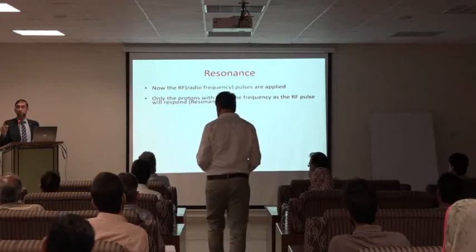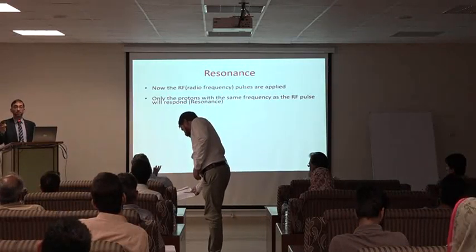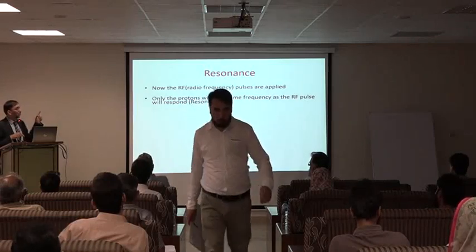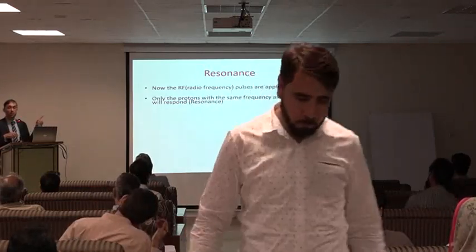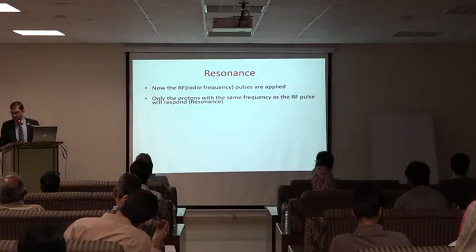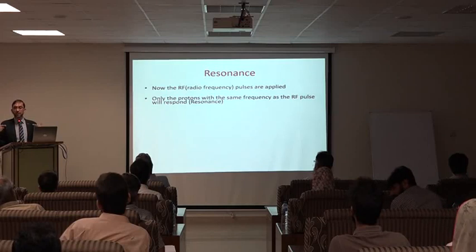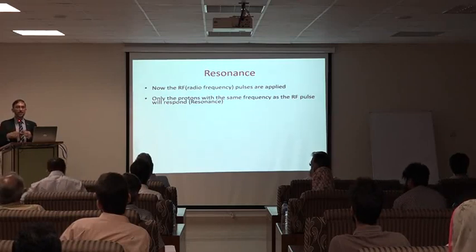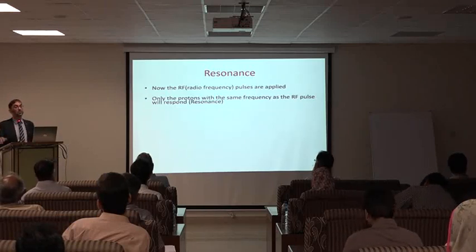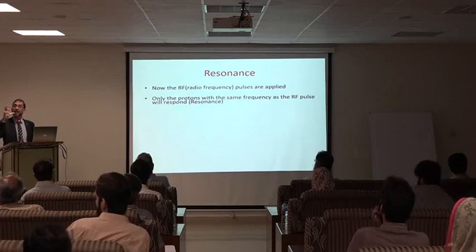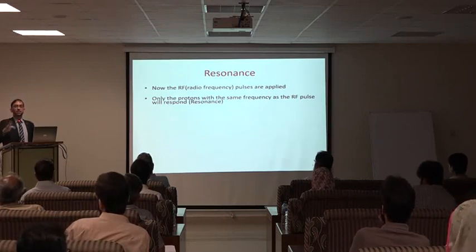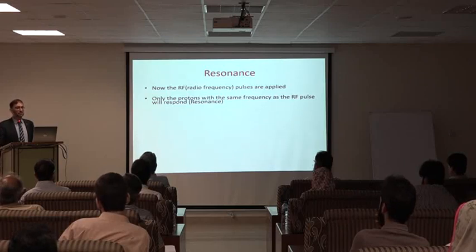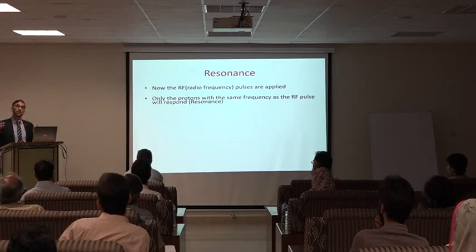The scanner tells you, if you want to image the knee, this is the frequency you should produce. If you are imaging the heart, this is the frequency you should produce. So only the protons with the same frequency as the RF pulse will respond. You just choose the knee, and the scanner itself will calculate what frequency the protons, the water molecules in the knee, have got. It will produce the RF pulse of that frequency. So when that RF pulse is transmitted, only the knee will absorb it. Only the water molecules in the knee will absorb it because of resonance, because everywhere else the frequency is different.